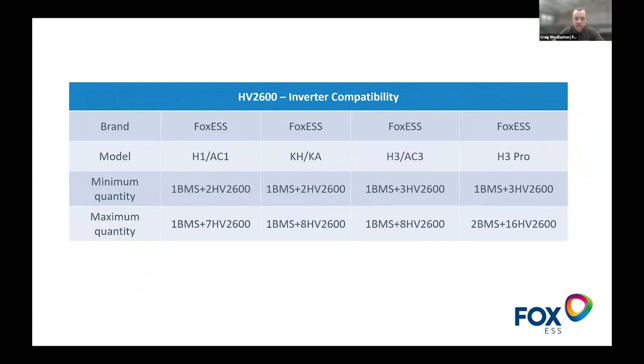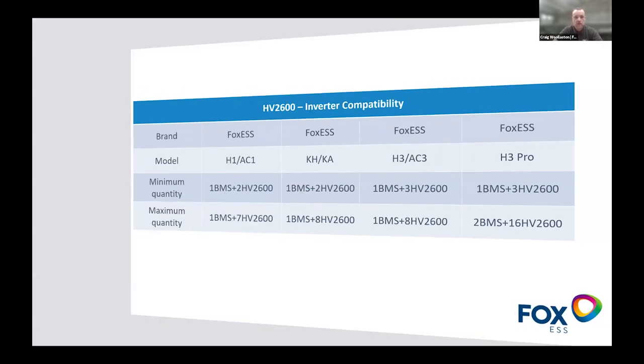That, again, because it's high voltage series installed, is subject to minimum and maximum quantities. This one does have a separate BMS - the Energy Cube's BMS unit is a battery called the master, whereas this has a separate BMS and then units underneath. So just be mindful that we operate within minimum and maximum quantities of the batteries to stay within the operating range of the inverter itself.